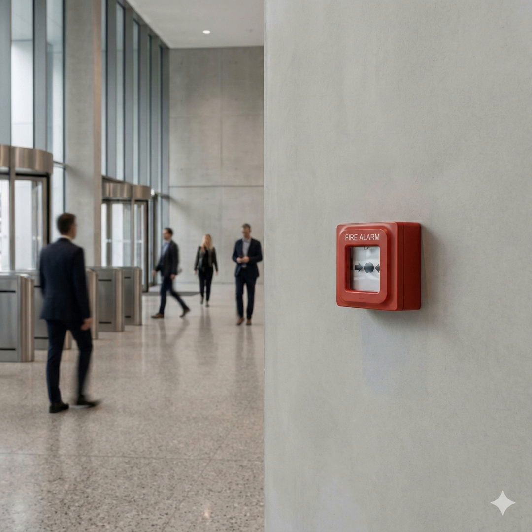Precision requires power, and fire alarm systems require continuous power, usually converting AC to a supervised 24 VDC supply. But the real security layer is the battery backup. What are the standards there? The NFPA 72 requirements are demanding. Standard commercial buildings require 24 hours of standby power plus 5 minutes of full alarm operation. This ensures that even during a long power outage, the system stays fully supervised and ready.